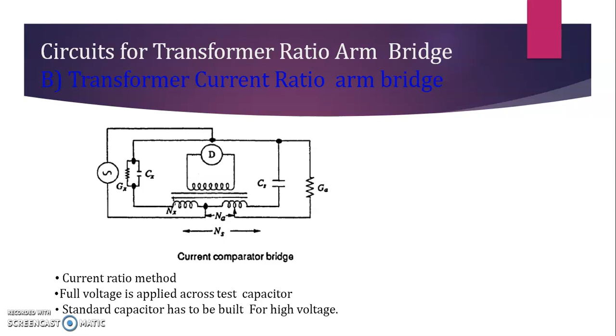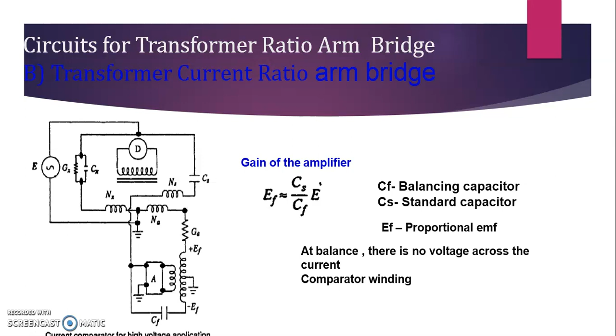So you can see this is the typical circuit used for a current comparator bridge, or you can say the transformer current ratio arm bridge. Now, as I was telling you that it is difficult to construct a precision conductance suitable for a high voltage application. Now, this difficulty is overcome by modifying the circuit, as you can see on your screens. This is done by generating a low voltage signal EF, which is proportional and is in phase with the supply voltage E. Okay. Now, at the balance conditions, these are the equations where Gx and Ga are unknown and standard conductances, and Cf is the balancing condenser.